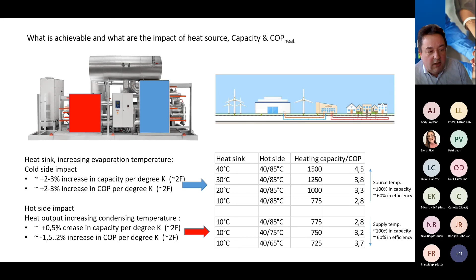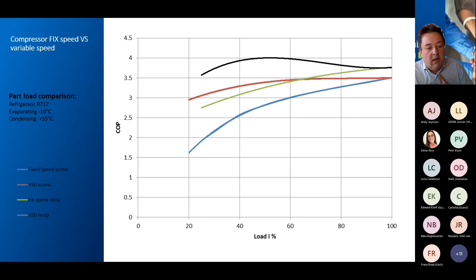Looking at a heat pump in case of capacity control, I have made a small curve here, and the black line is the COP of a reciprocating compressor that is speed controlled. You see that the curve is increasing in COP as you go down in capacity. That's the fact with the reciprocating compressor: the performance increases because the delta pressure and the losses in pipes and valves go down as you lower the RPMs. The differential pressure in a pipe gets smaller as you lower the mass flow. Eventually there are also mechanical losses in the compressor, and that means at around 50% it actually drops in COP again.